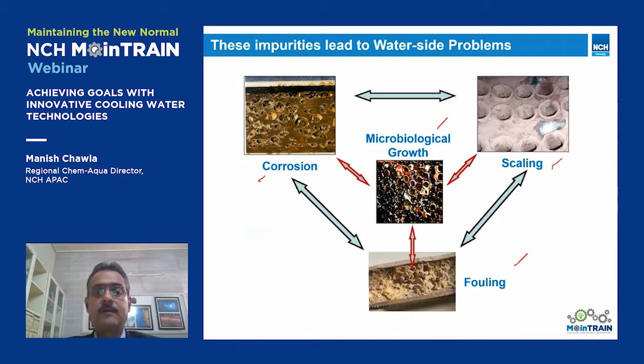Let's briefly see what these four problems are. Scaling is basically a hard, tenacious mineral deposit formed at the heat transfer surface. When the concentrated cooling tower water comes to a hot surface—like a condenser in your chiller or any heat exchanger surface—the skin temperatures are high. This water, having more TDS and especially salts like calcium and carbonate, cannot remain soluble. Its solubility will be exceeded, so it precipitates out and forms a layer like this. This is what we call scaling.